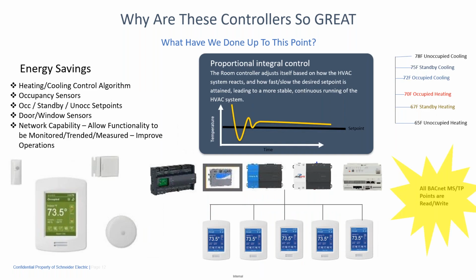There's also an aspect to these controllers that we use for energy savings, right? Energy savings is a big deal these days, and we try to build that into each one of these controllers. Each one of them has a heating PID and a cooling PID, so that you know where you are within that spectrum. So you don't have to go full heating or full cooling if you have modulating outputs.